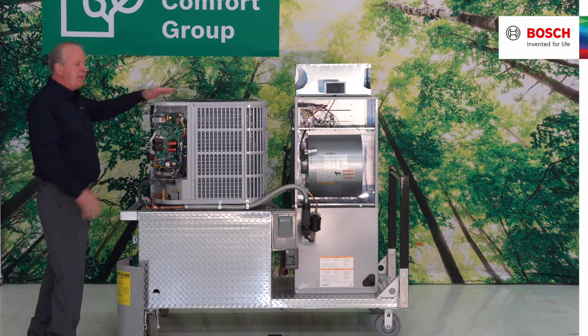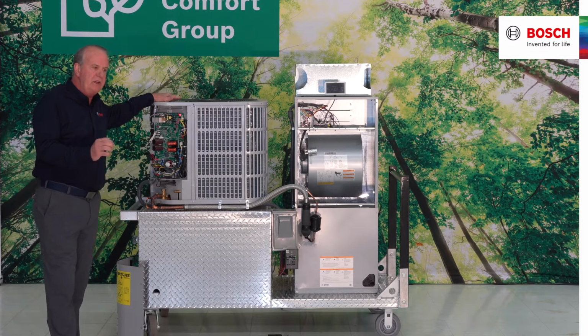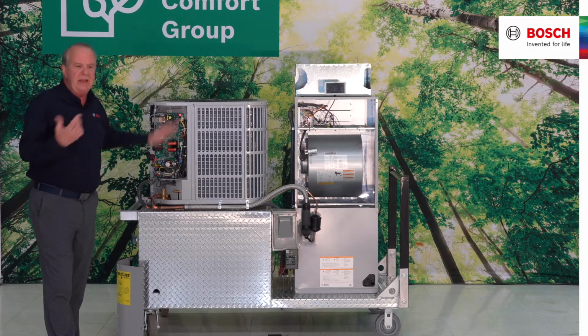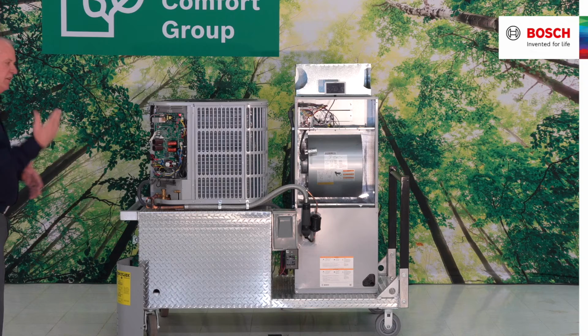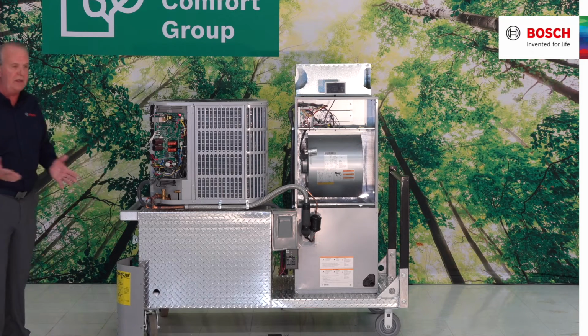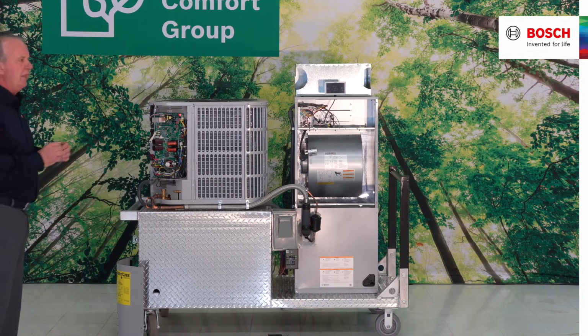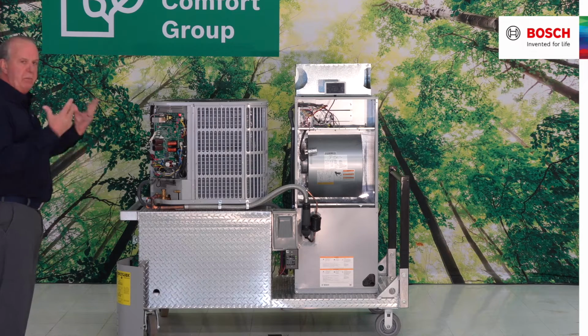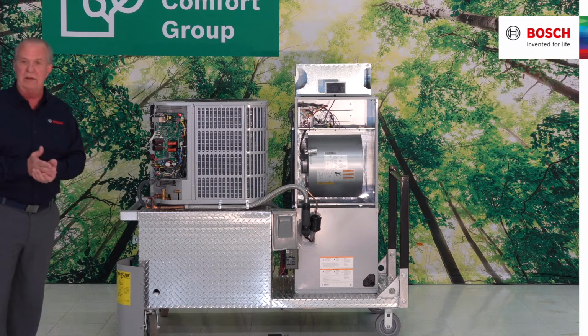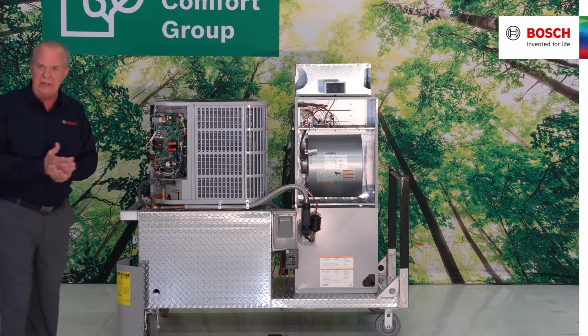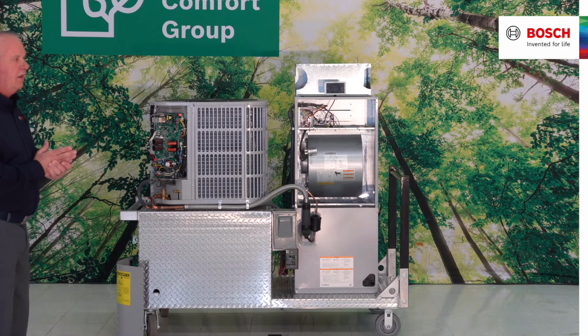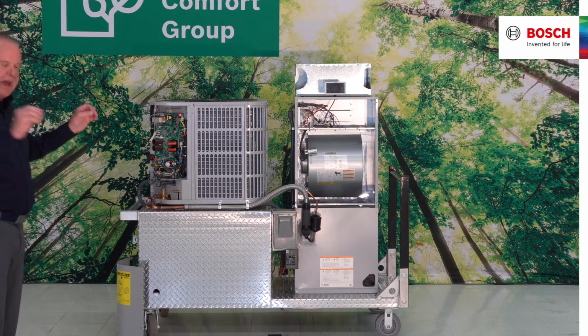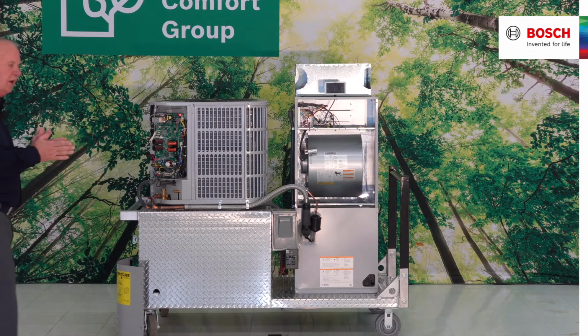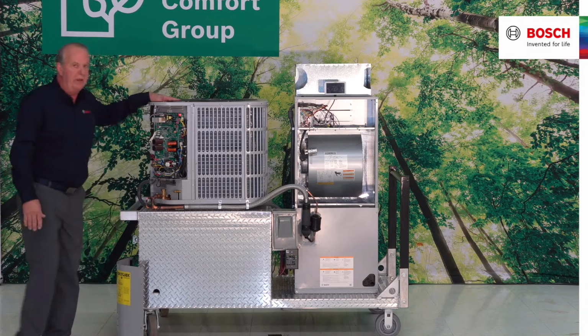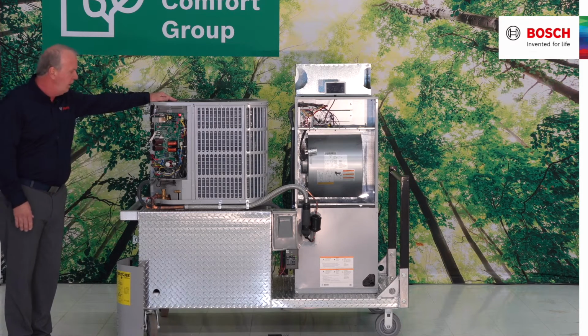Now, we had mentioned earlier about the pressure transducer maintaining a constant target evaporator temperature. So understanding that the variable BTUs that you have there, 9,000 to 40,000 in the 3-ton, once again 15,000 to 66,000 in the 5-ton, knowing that we have that pressure transducer that's going to maintain, in this case out of the box, a 46-degree evaporator target temperature in the cooling cycle and a 108-degree evaporator coil temperature in the heating cycle, straight out of the box. Understanding the variable capacities and the load matching and understanding how the pressure transducer maintains that targeted temperature is what makes this a really special piece of equipment in my experience. So having said that, hopefully that's clear enough.